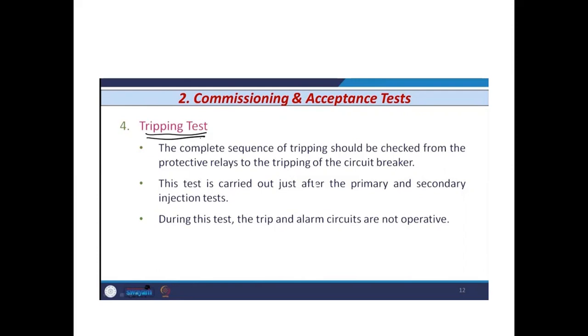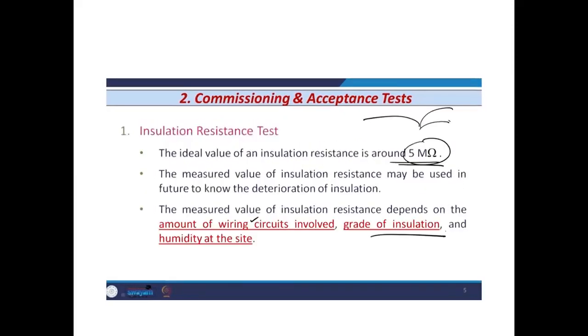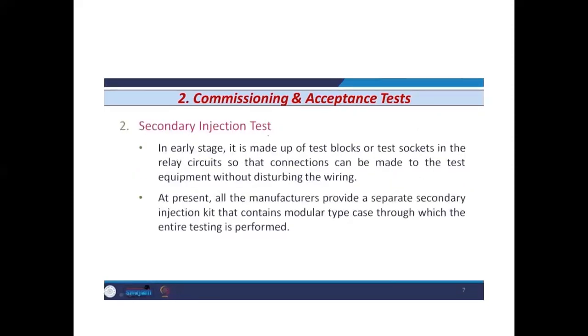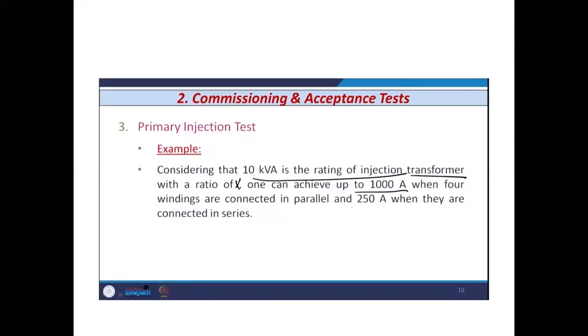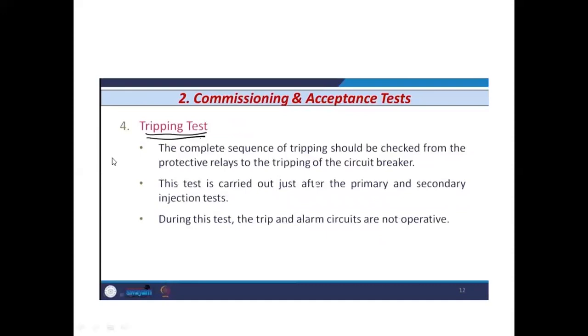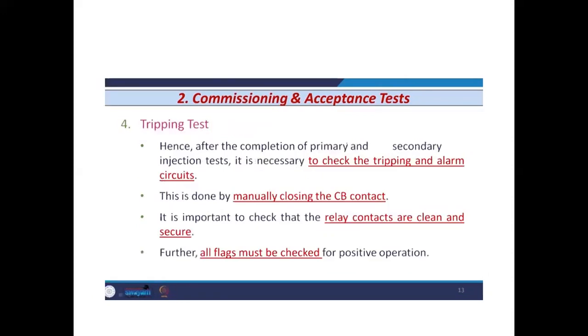The first in this sequence was the insulation test, followed by the secondary and the primary injection tests, and then we have the tripping test. So this test is carried out just after the primary and secondary injection tests. This one is fourth in sequence. During the injection tests, the trip and alarm circuits are not operative. Hence, after completion of the primary and secondary injection tests, it is necessary to check the tripping and alarm circuits. This is done by manually closing the circuit breaker contact.